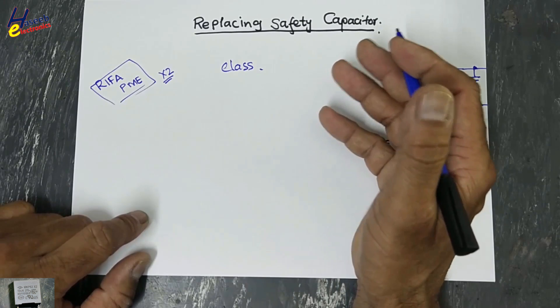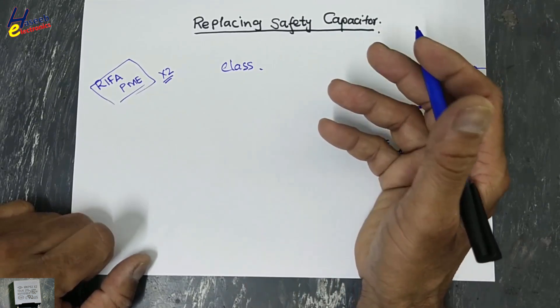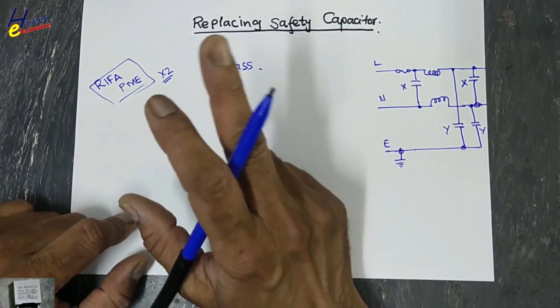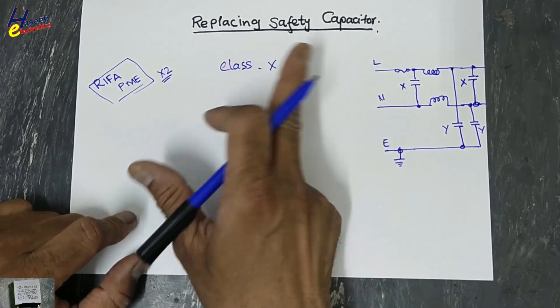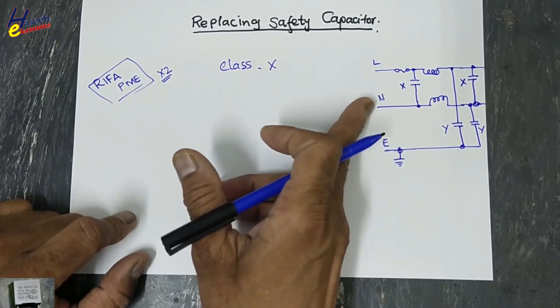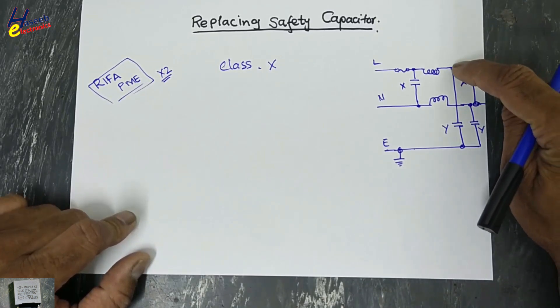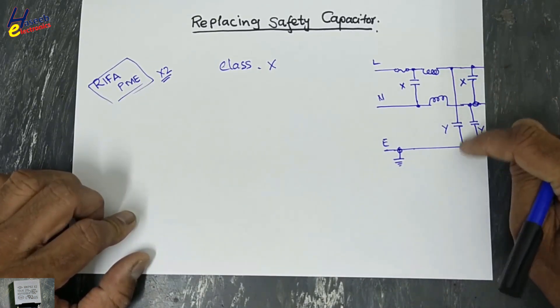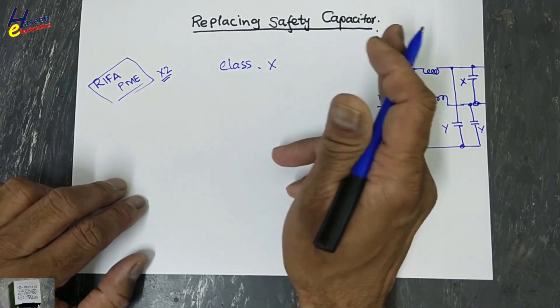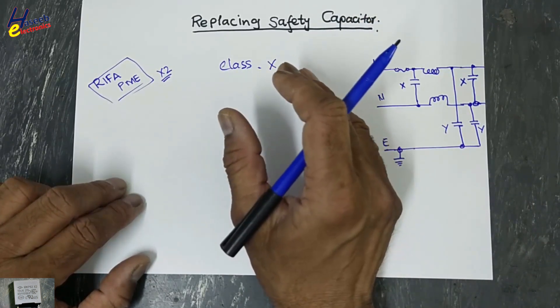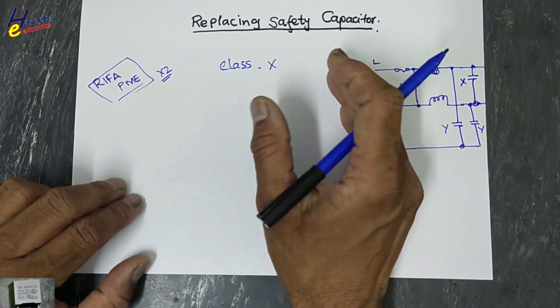Class X1, X2, X3, Y1, Y2, Y3, whatsoever. Either it is class X or class Y. Class X capacitor is used in line and neutral. Class Y capacitor is connected between line and earthing point, neutral and earthing point. X1, X2, X3 will depend on the voltage ratings and the circuit category.